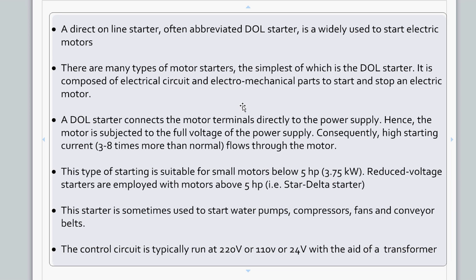It is composed of electrical circuits and electromechanical parts to start and stop the electric motor. A DOL starter connects the motor terminals directly to the power supply, so the motor gets the full voltage. Initially, it can draw high current, three to eight times more than the normal current.